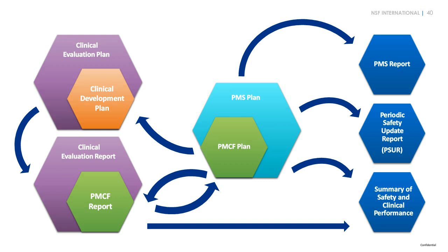Finally, PMS and PMCF activities should also be considered in the PMS report, in the periodic safety update report, and in the summary of the safety and clinical performance. The summary of safety and clinical performance should also include a summary of the clinical evaluation.